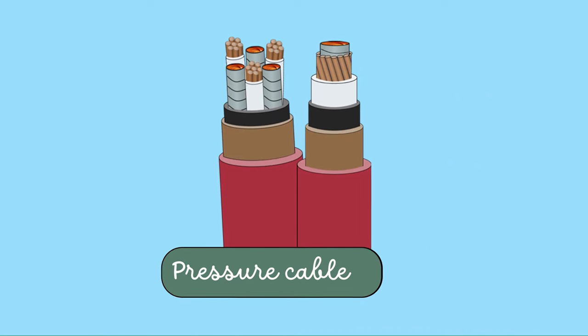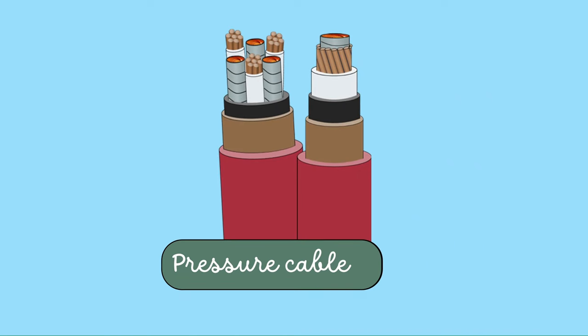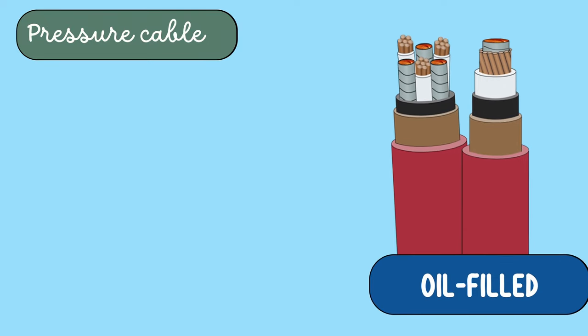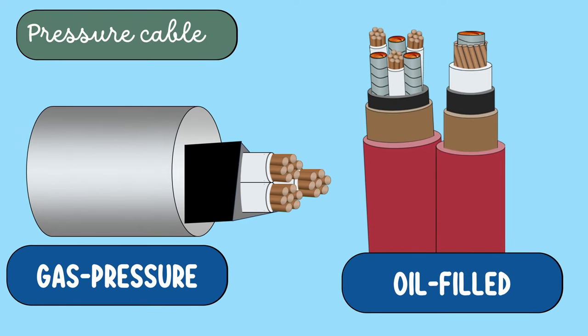Instead, pressure cables are used. In pressure cables, the voids are eliminated by increasing the pressure of the component. It can be done either using oil or gas. Accordingly, they are classified into oil-filled cables and gas-pressure cables.